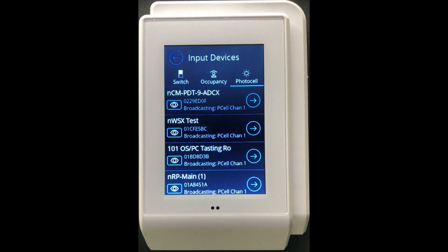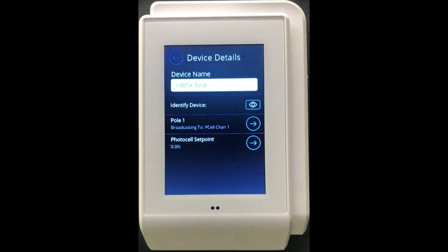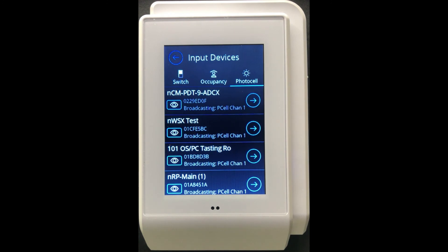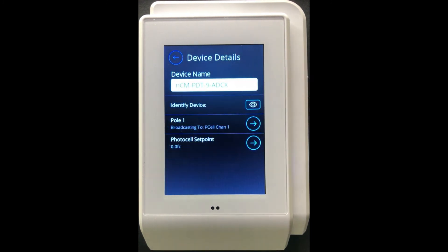You have the same flexibility when it comes to photocell — go into the photocell section, select any one of the photocells, and associate the poles to broadcast to any one of the 16 photocell channels. You can even go one step further with photocell and adjust the photocell set points. You get lumen input readings for that photocell and you can also configure auto calibration directly on screen of the NWSX.